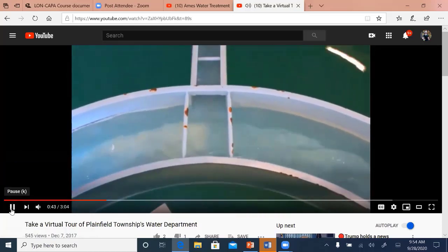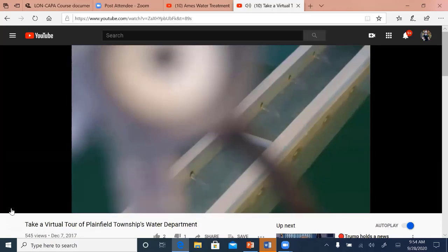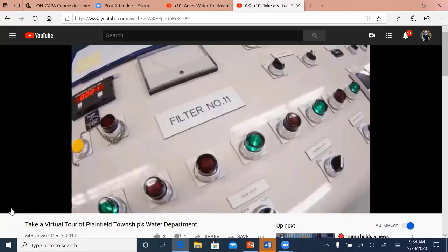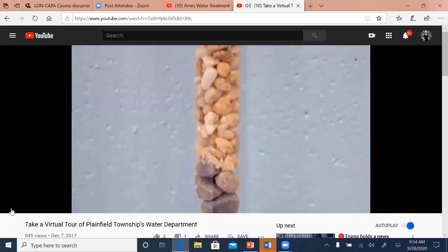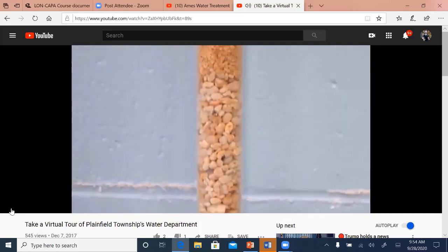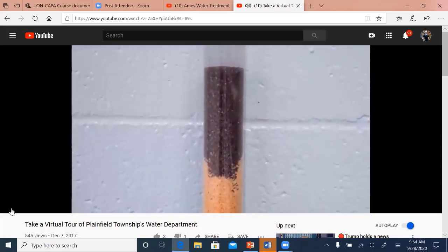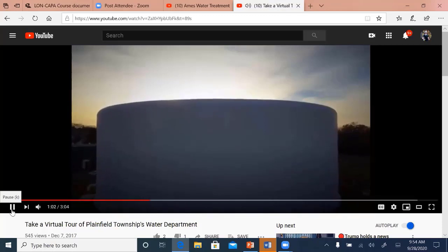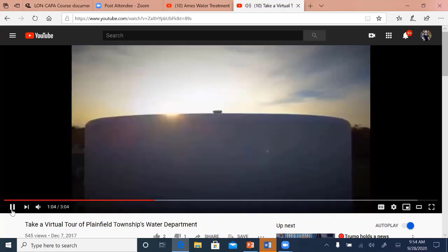The slurry saturates the water. The mixture causes heavy particles like calcium and magnesium to sink to the bottom, while the softened water goes to the filters. The filters consist of bell-shaped tubes that contain layers of a semi-permeable substance, including gravel, fine sand from Iowa, and anthracite coal. After the water is run through the filtration system, the water is...